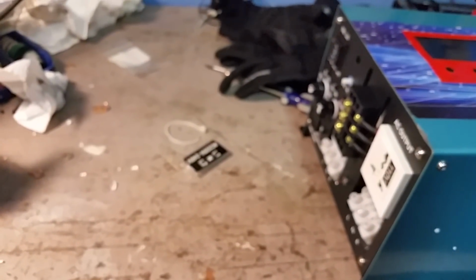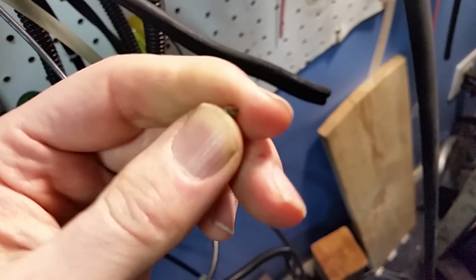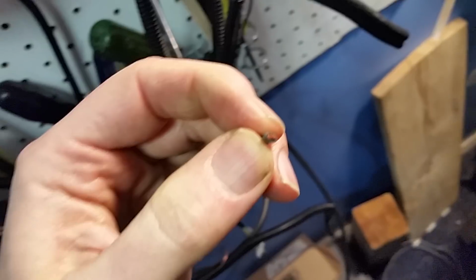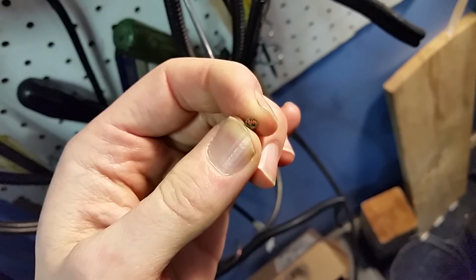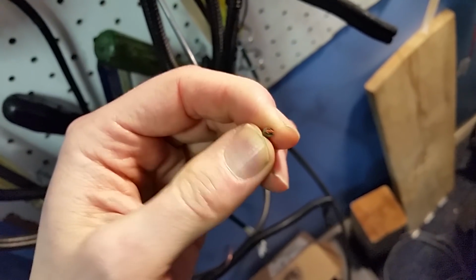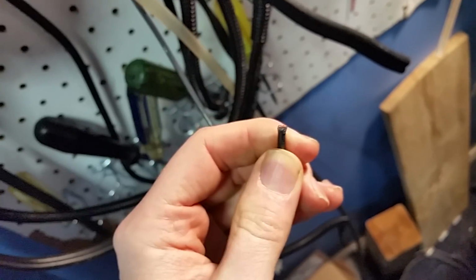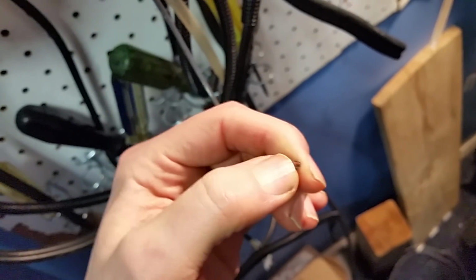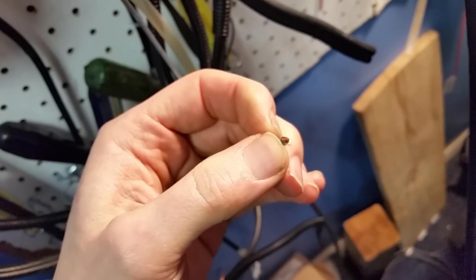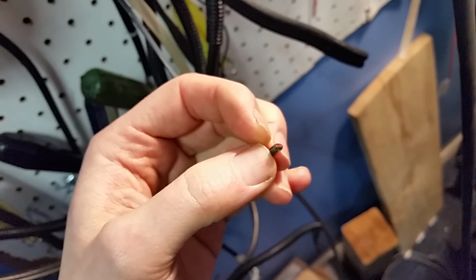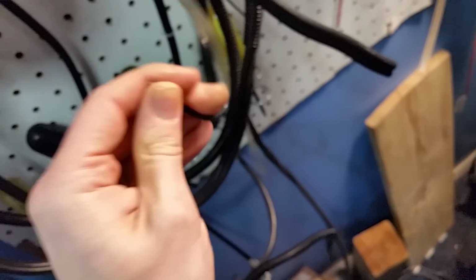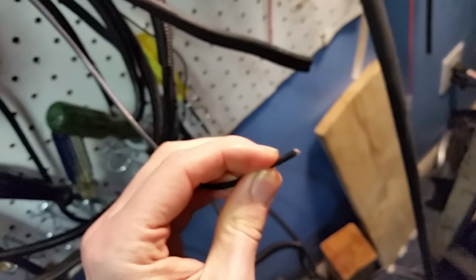I have some 12 gauge wire here, which is pretty close to that. That wiring is rated for a 20 amp circuit breaker, meaning it should never exceed 20 amps on a continuous rating. Really, electrical code states you shouldn't exceed 80% of your circuit breaker's rating, so that's 16 amps. This can do 16 amps safely and continuously, no problem.